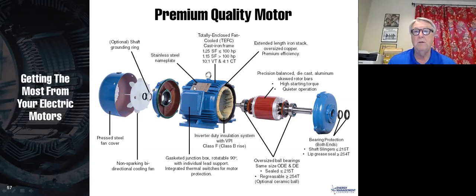Well, first of all, there's a stainless steel nameplate, sorry. And the stainless steel nameplate is very important because arguably, if you want to replace a motor or you want to get a motor repaired, when you bring your motor into our repair shop, do you know the very most important thing on that motor is the nameplate, because that tells us what that motor is. If it doesn't have a nameplate, it becomes much, much more difficult.